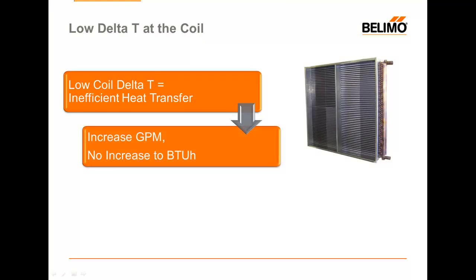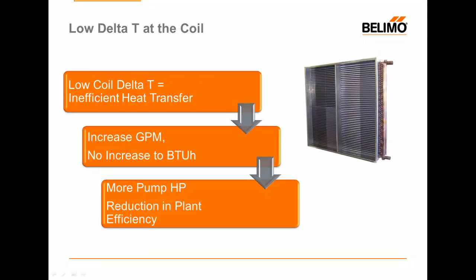Low coil delta T means that I have inefficient heat transfer — I sent very cold water to my coil and it's still pretty cold when it heads back to my chiller plant. This is typically caused by increased GPMs. I'm flowing more water to my coil but due to my low delta T I'm not generating an increase in the total number of BTUs produced, so I cannot offset any additional load in that space. I'm pumping more water and not creating any more BTUs, which means I have to use more pump horsepower and I'm reducing my overall plant efficiency.